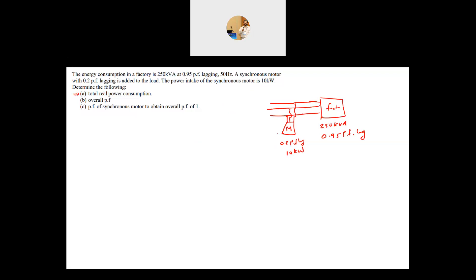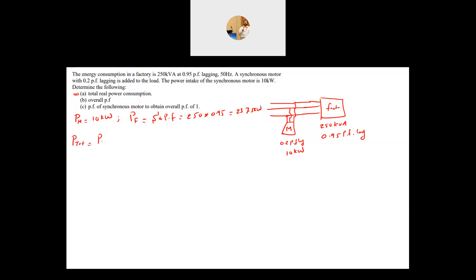Part A: Total real power consumption. The power of the motor is known as 10 kilowatts. The power of the factory equals S times the power factor, which is 250 kVA times 0.95, giving 237.5 kilowatts. Therefore, the total real power is P_motor plus P_factory, which is 10 plus 237.5, giving 247.5 kilowatts. Very straightforward.